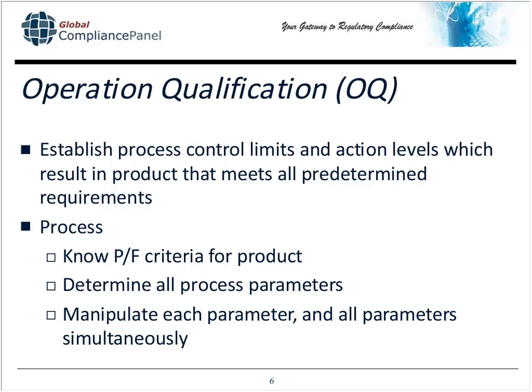And what many firms do is they take advantage during this OQ to not just look at the absolute cliffs, but to bring it in some percent to have action levels. So they can proactively determine, well, I'm going to SPC these temperatures, and I've determined that even though my high temperature limit is, let's say, 170 degrees, I'm going to set my action limit at 160 degrees. So I know that I've got to take action when it goes above 160 degrees, because when it hits 170, I'm out of my validation requirements, and then I have to reactively fix my piece of equipment.